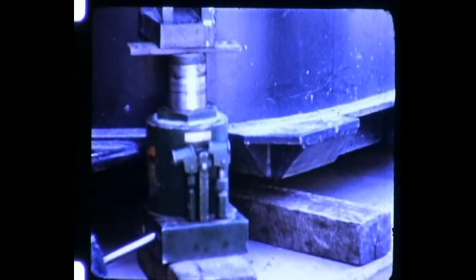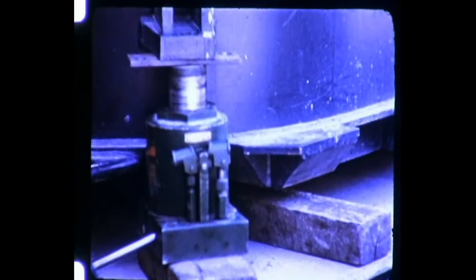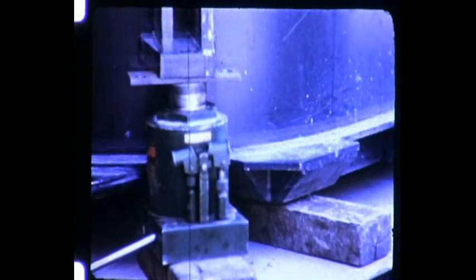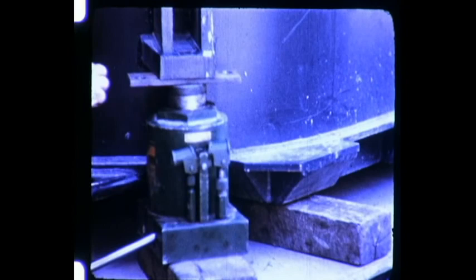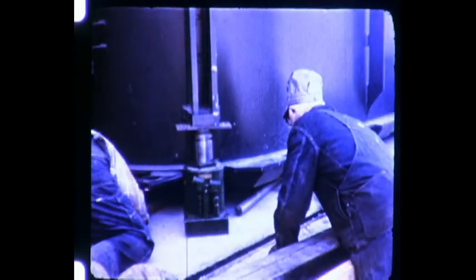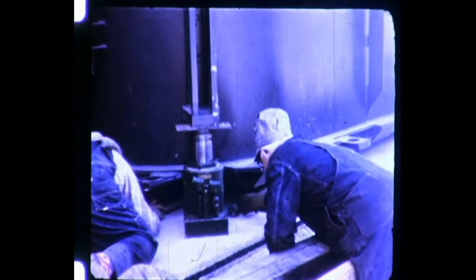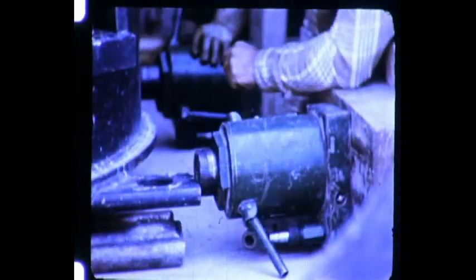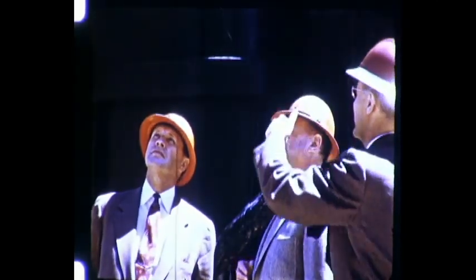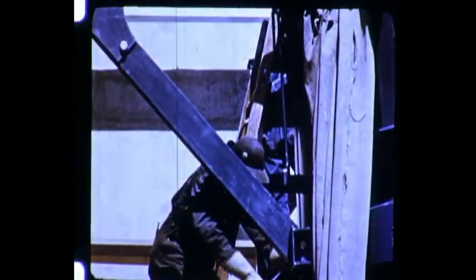The hydraulic jacks let the unit down to a height just sufficient to accommodate small rods, which, as in the Delta Station job, are used to shift the unit slightly for final positioning. To accomplish this, the jacks are used horizontally. With the moving job done, power company officials inspect job progress. And the contractor starts installing the auxiliary equipment.